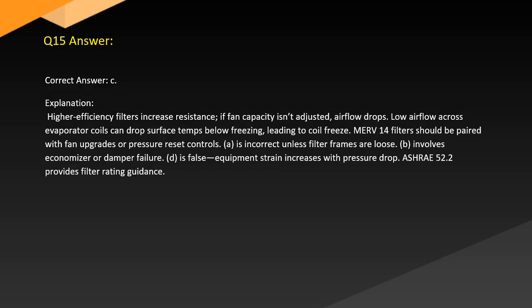Answer. Correct answer: C. Explanation. Higher efficiency filters increase resistance. If fan capacity isn't adjusted, airflow drops. Low airflow across evaporator coils can drop surface temps below freezing, leading to coil freeze. MERV 14 filters should be paired with fan upgrades or pressure reset controls.